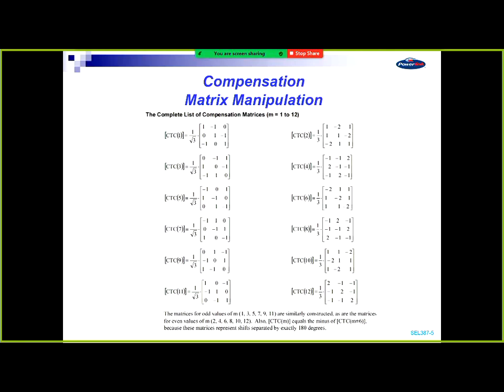So from 0 to 12 is what you can select from. The 12 gives you 360 degrees, so you're making no difference at all at 12, but you're taking out the zero sequence. 1 is 30 degrees, 2 is 60 degrees, so YD 1, 2, 3, 4, and so on like that till you get to the 12.